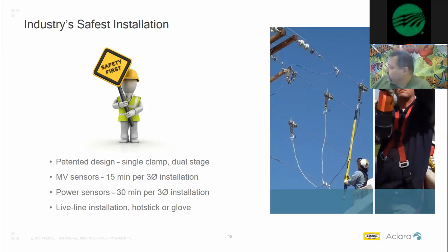So the clamp actually goes in a two-stage format. When you looked at the sensor previously, you'll notice that it has a larger channel in the center, and you're wondering to yourself, how could that channel fit a small size conductor or even a larger size? So for instance, putting it on a piece of 2-aught, when the two halves of the sensor close down onto the conductor and meet together, there's a second stage clamp mechanism inside that sensor body. Once that hotline clamp or our eye bolt is twisted, it will continue to pull down that second stage clamp around the conductor and secure it from sliding on the conductor. So that's how we're connecting metallically to the actual conductor itself.